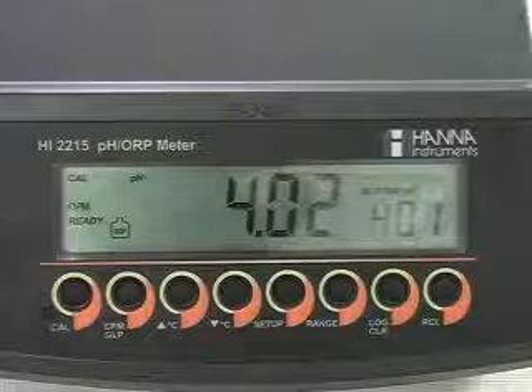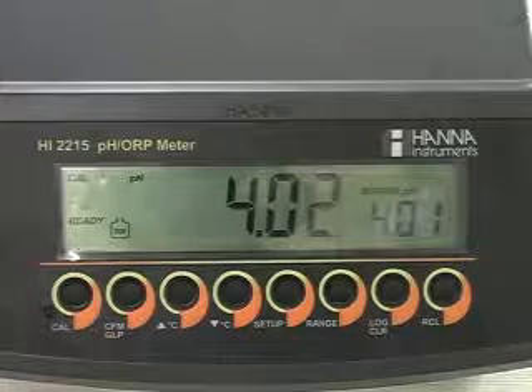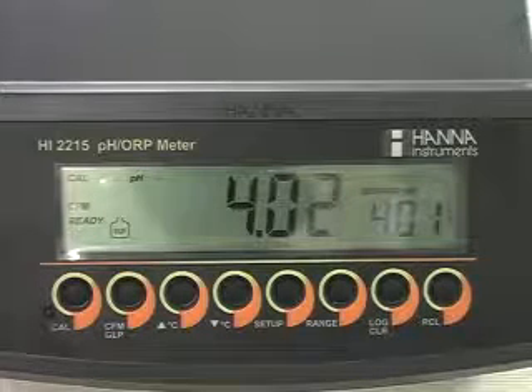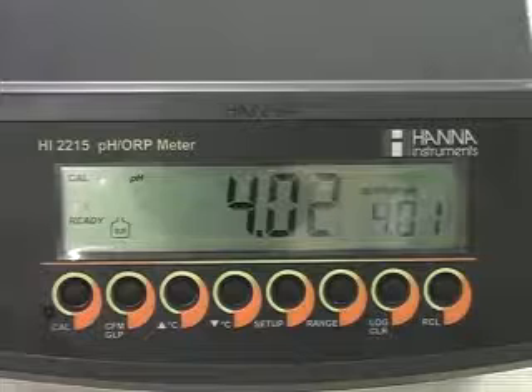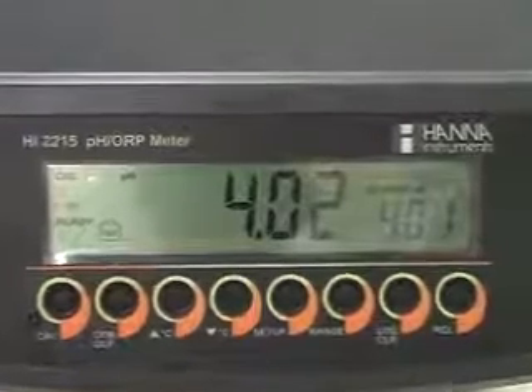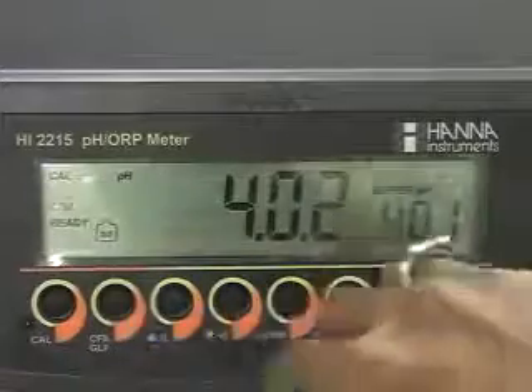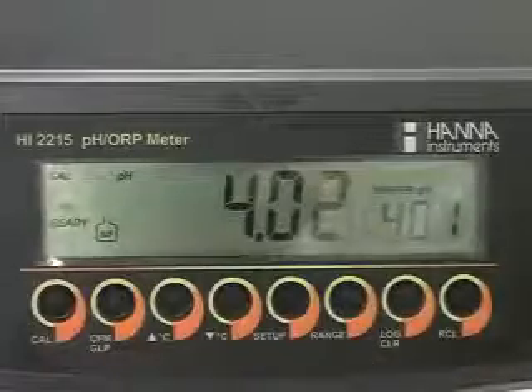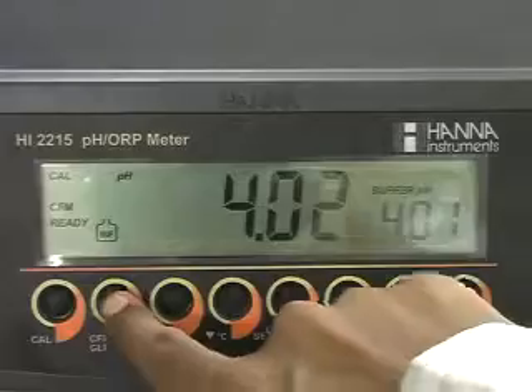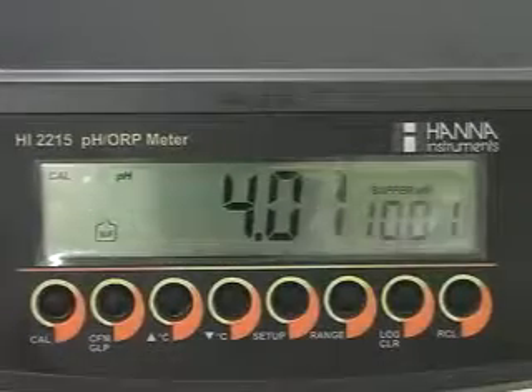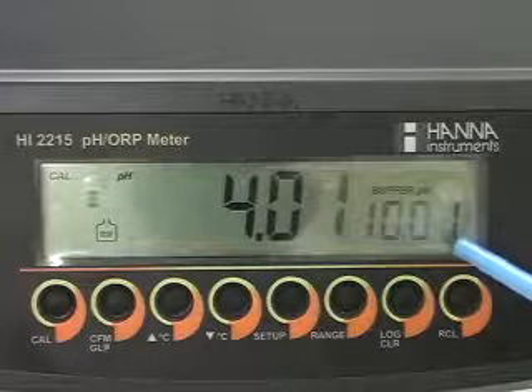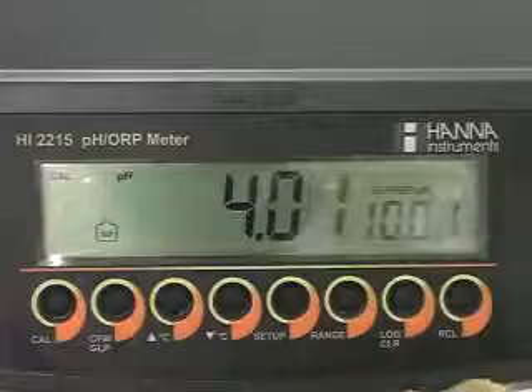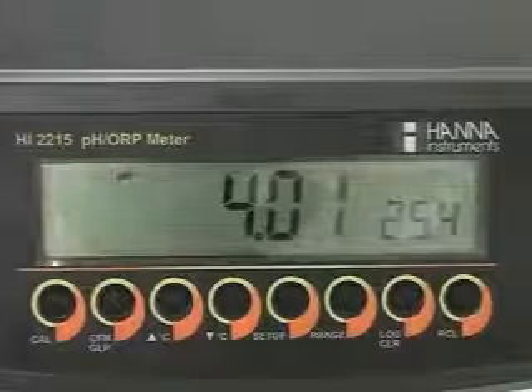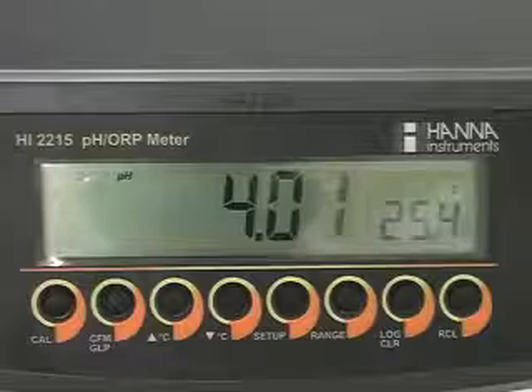When the reading is stable and close to 4.01 buffer, the ready tag and blinking CFM tag will appear on the display. At this time, press the CFM key to confirm the second calibration point. After this 2-point calibration, the instrument will show you the third point, that is 10.01. At this time, please press CAL to exit the calibration mode. The instrument will memorize the calibration data and it will return to measurement mode.